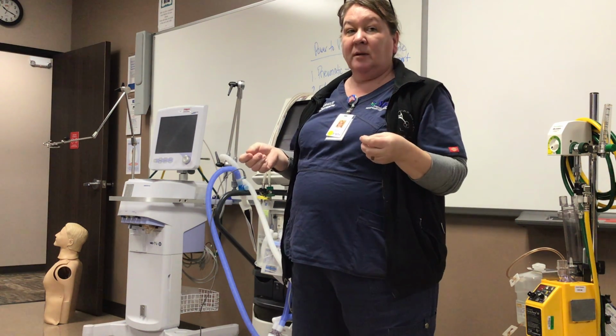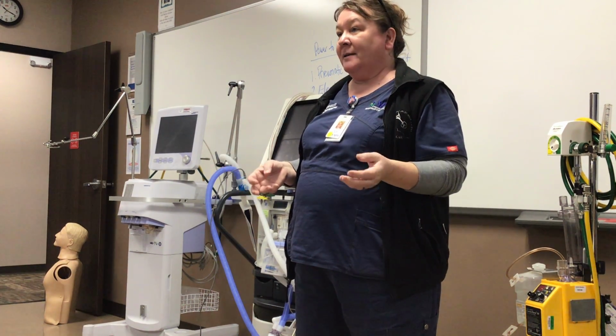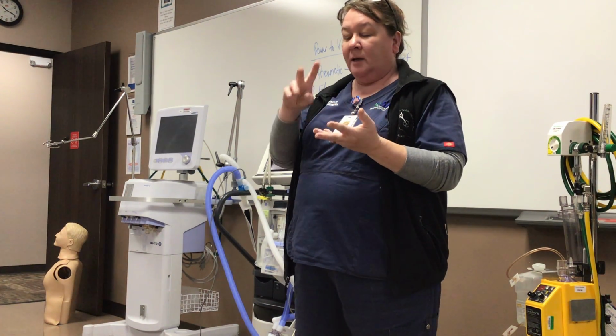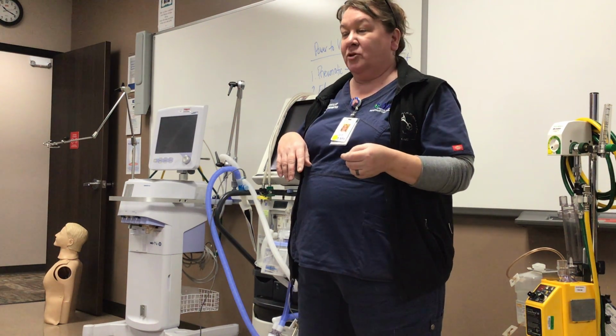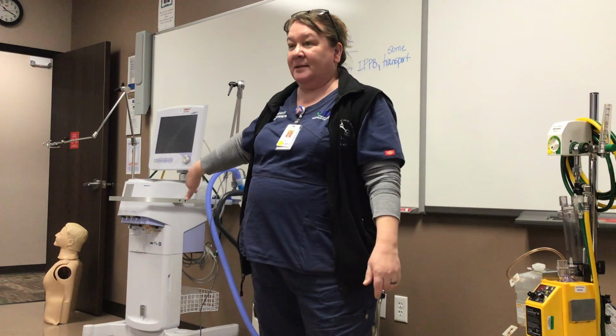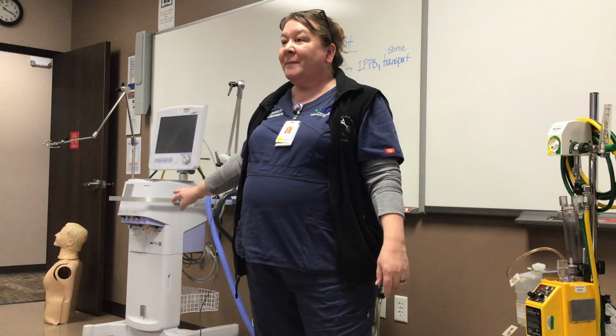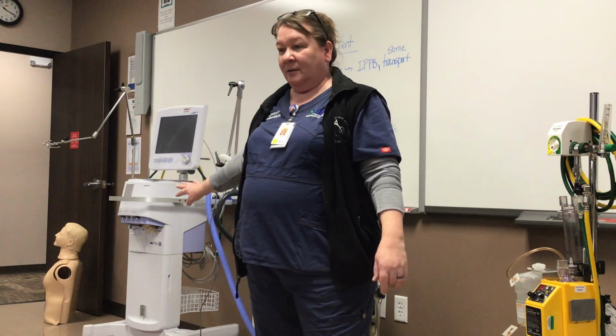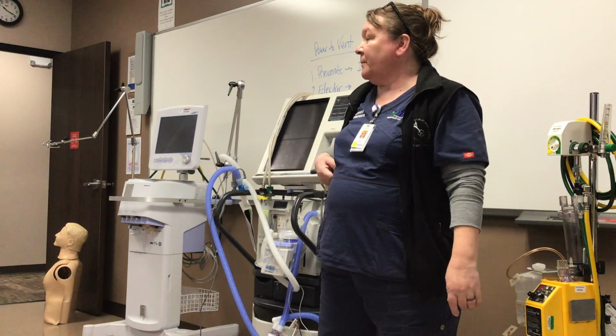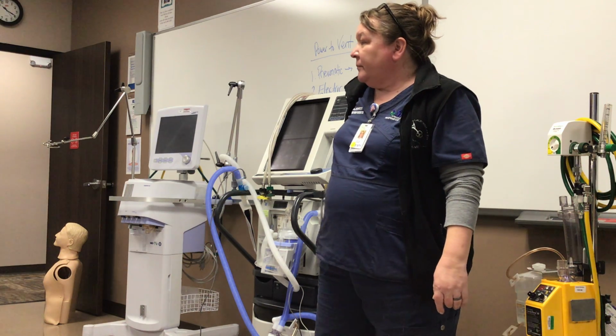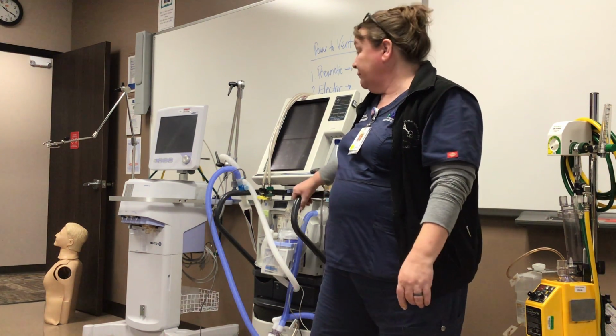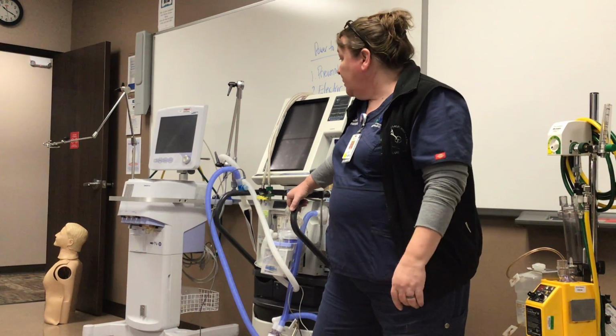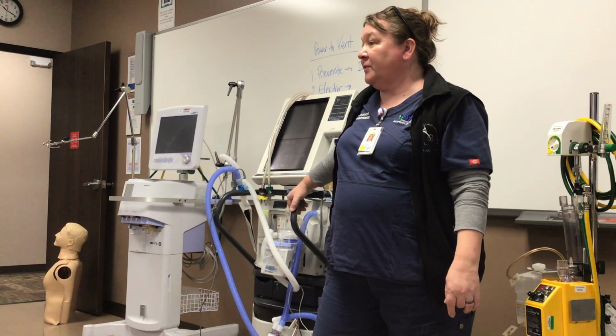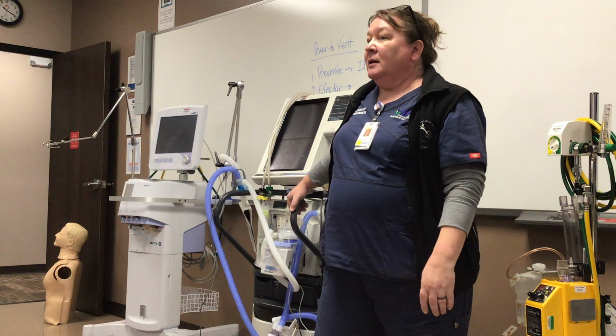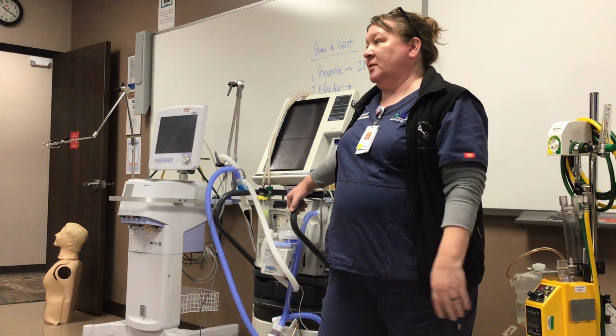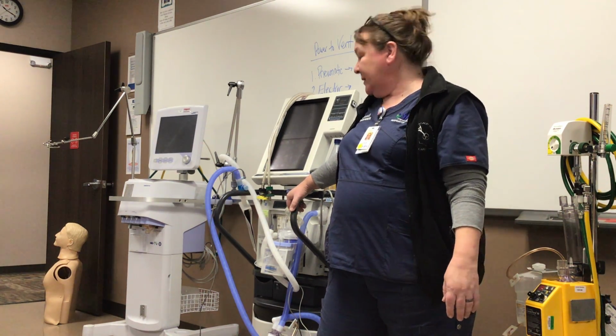The reason this is important is because exhalation valves can go bad. They can also get filled with water or sticky, icky stuff from nebulizer treatments, which is why we put filters on the exhalation side. Mucomyst and some of that stuff will wreak havoc on your exhalation valve. Yes, Mitch? You have a patient on the vent, how long before you change those filters? Only if needed, if they're soiled, or you think there's a problem. If you're giving Mucomyst to somebody, you're going to have to change them because it's going to get gross in there. Otherwise it's just as soiled.